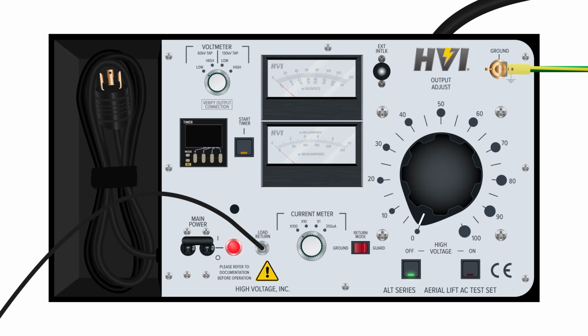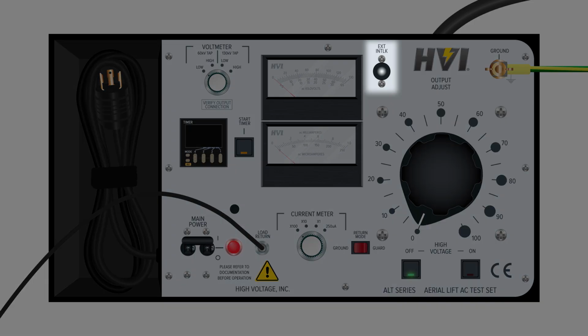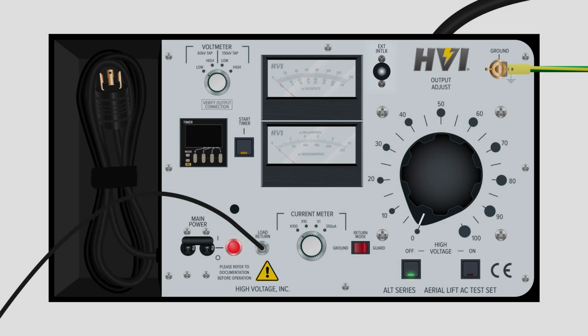Make note of how the return mode switch is set. See the guard ground explanation later in this video, or the user manual for which return mode is appropriate for different settings. Now, ensure the external interlock key is in place. Please note, the high-voltage circuit cannot be energized without the external interlock in place.